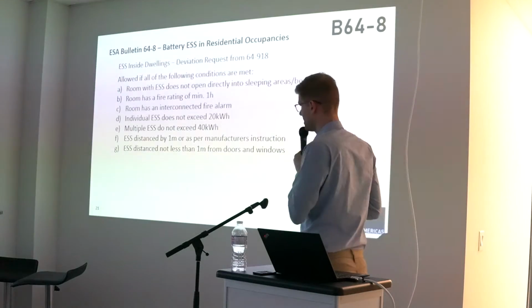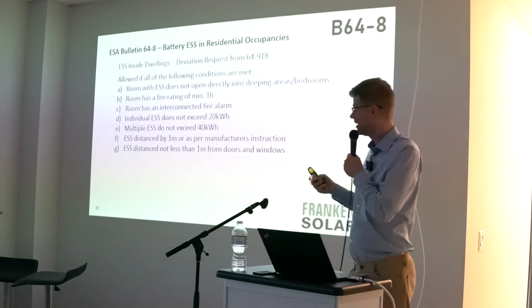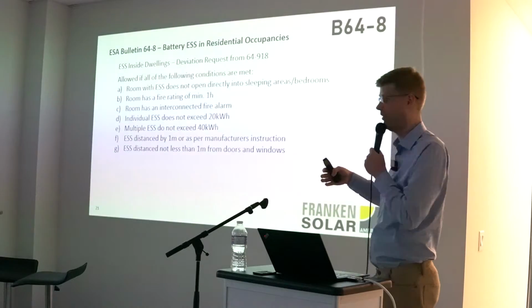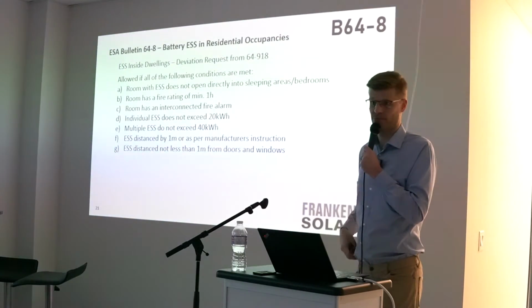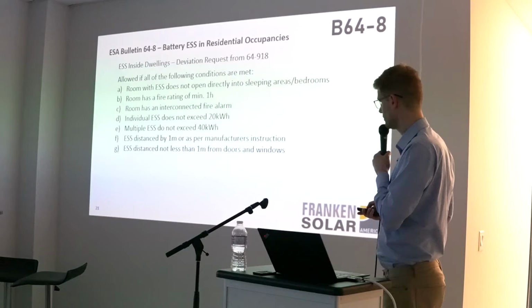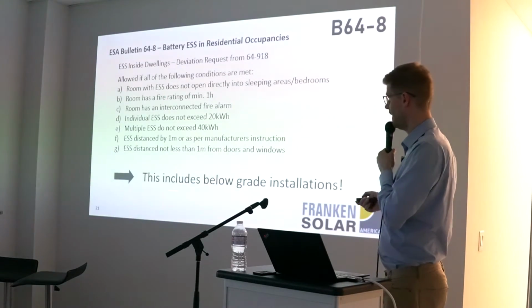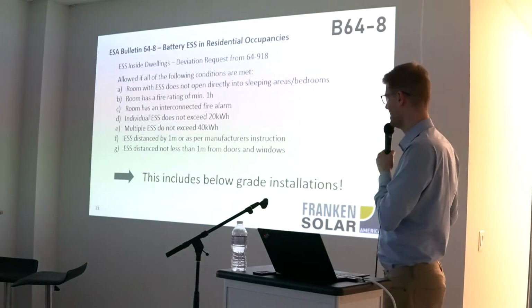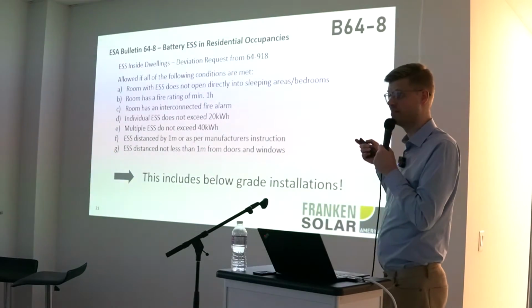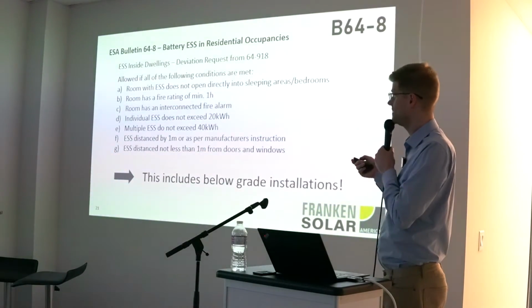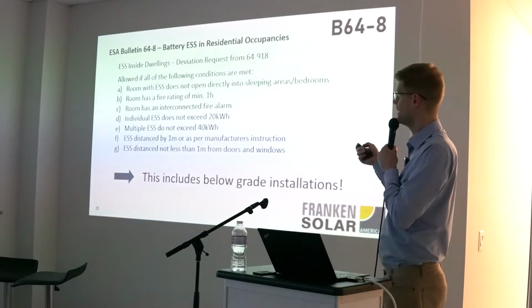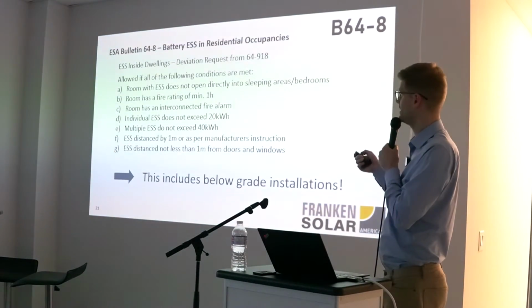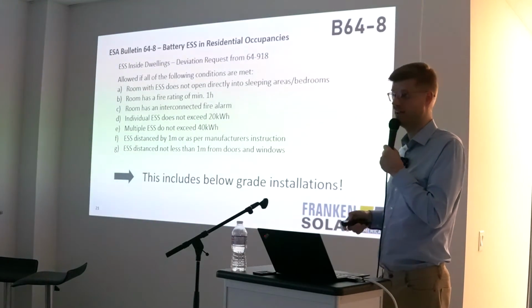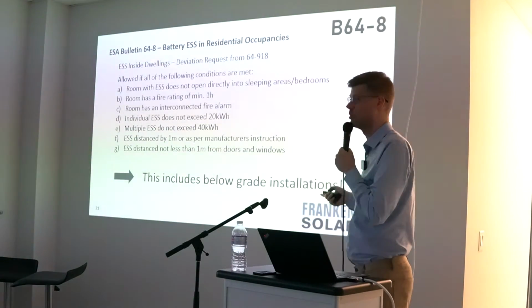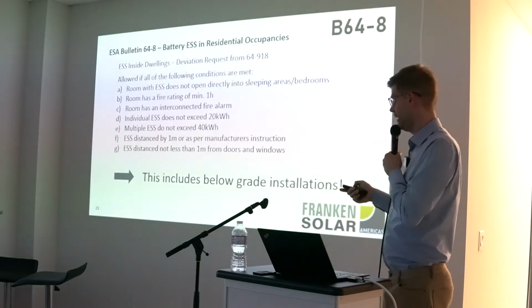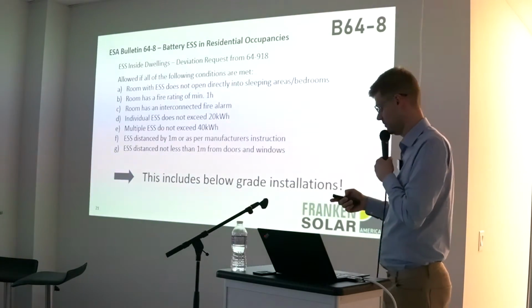And the storage system has to be distanced at least 1 meter from any egress path or window that is in that room or building you put it in. And the most important thing, and that goes to your question, is that this includes even the below grade installation, with that deviation request referencing Bulletin 64.8 and 64.918 in the code. And that's typically what's being done right now for most of the installations for battery storage.